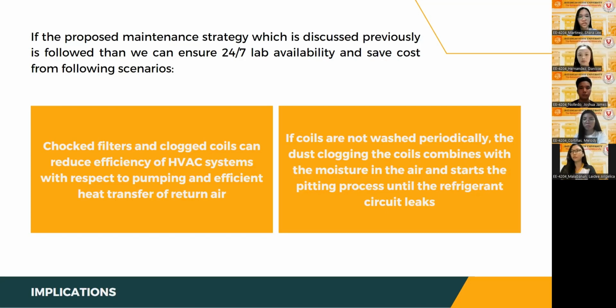First, choked filters and clogged coils can reduce the efficiency of HVAC systems with respect to pumping and efficient heat transfer of return air. The choked filters increase static pressure drop in the air handling unit, which increases the motor current to the point that airflow starts to decrease in the central ducting system and a loss of cooling or heating occurs. Similarly, when a coil is clogged, heat transfer is reduced, and the air is not cooled or heated up to the design specifications. The combined effect of choked filters and clogged coils can reduce overall system efficiency by 13 to 15% and increase electricity bills correspondingly.